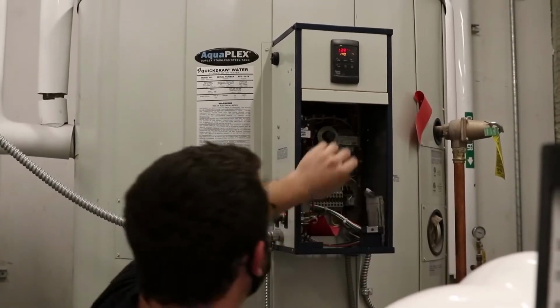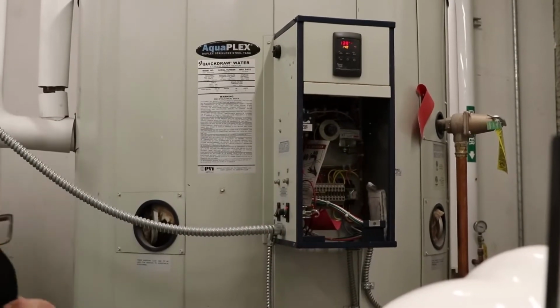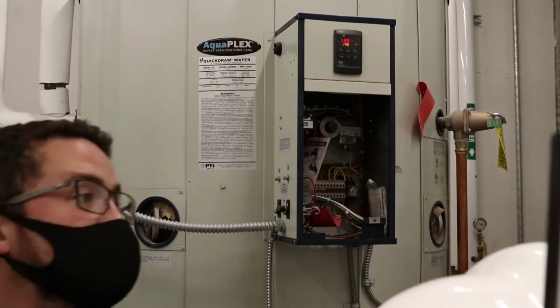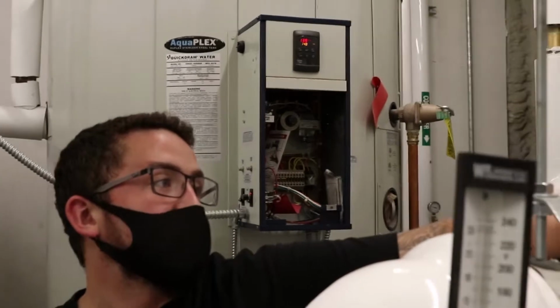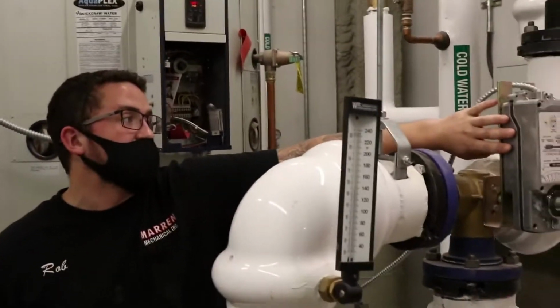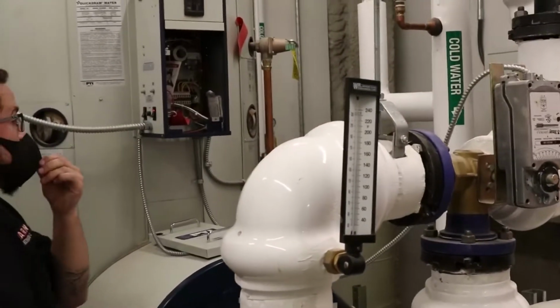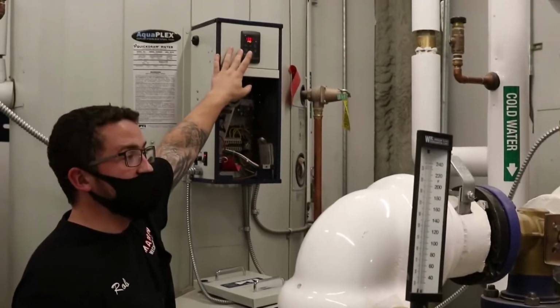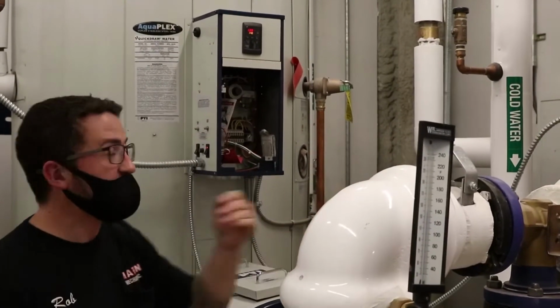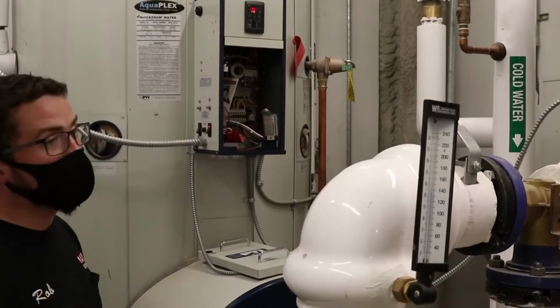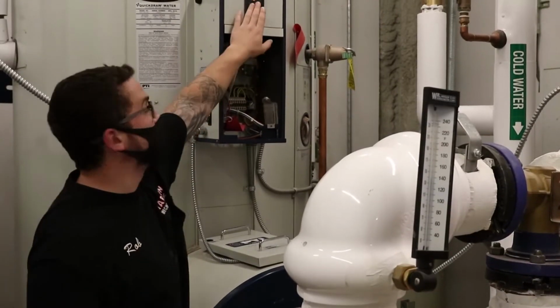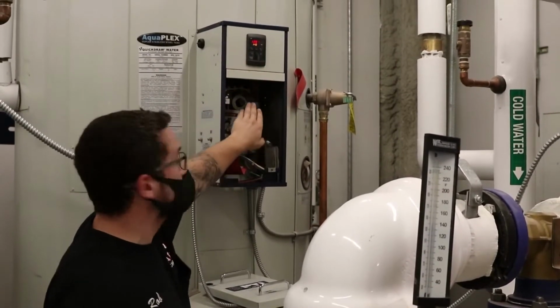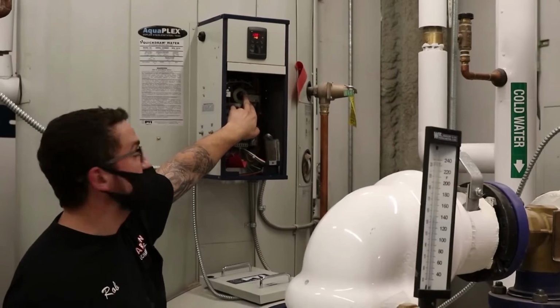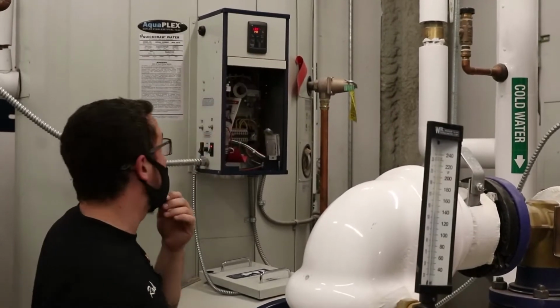That covers it as far as what controls the operation of this water heater. So to summarize, you have your boiler water control valve opening up, allowing hot water to flow through the heat exchanger. This happens until the set point is met, at which time this valve will close. And if you're going to make any changes to your primary set point, you just need to consider the upper operating temperature and set that 10 degrees higher than your set point.